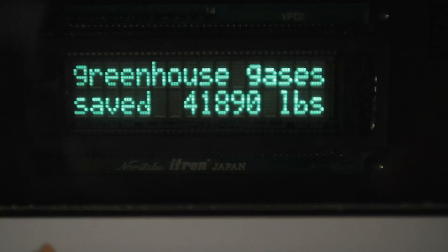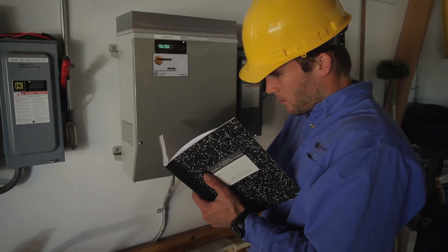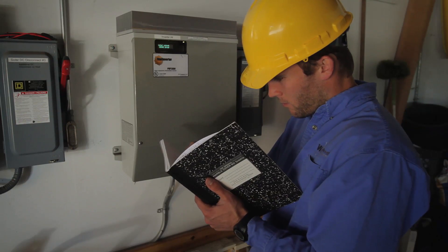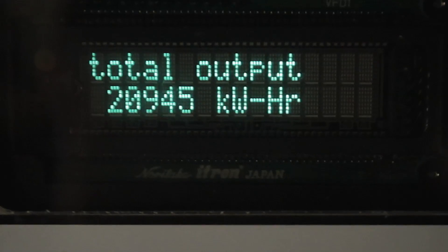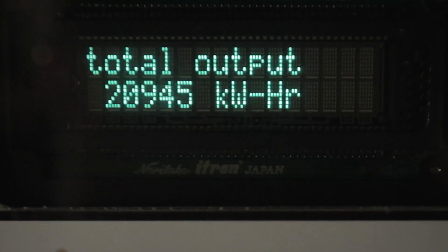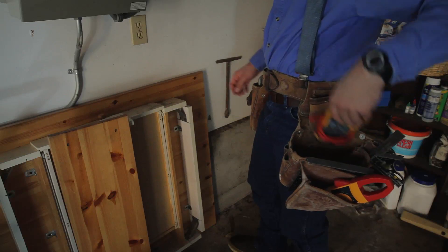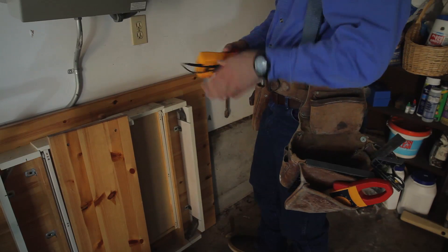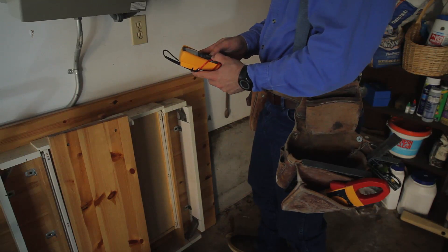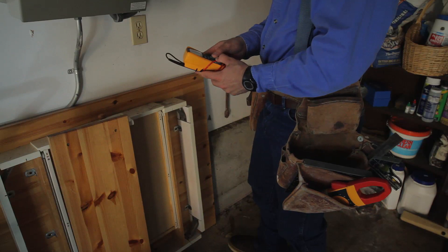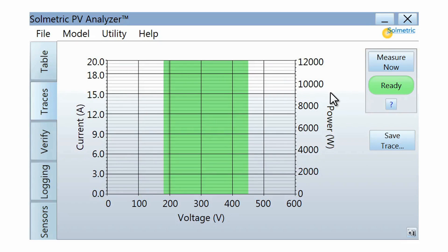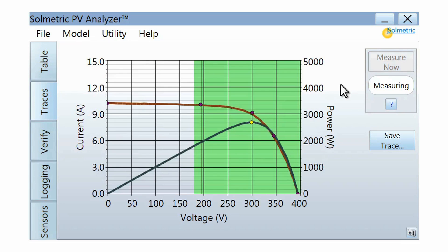There is a wide range of PV performance verification methods. The most basic method is to compare the power output of the inverter readout with the design power output specification. Using a multimeter and a clamp meter to measure key string parameters is a common approach. The most comprehensive method of performance verification is to trace the IV curve of each PV string and to compare the curve with a detailed performance model.